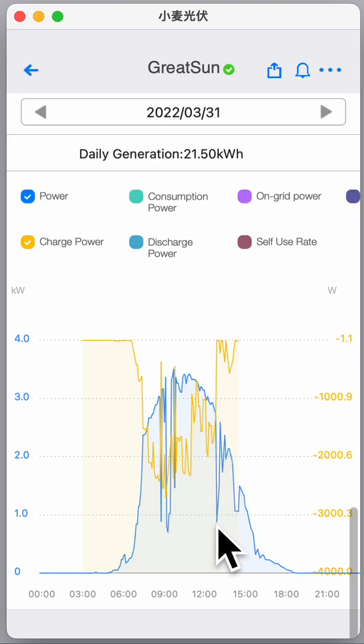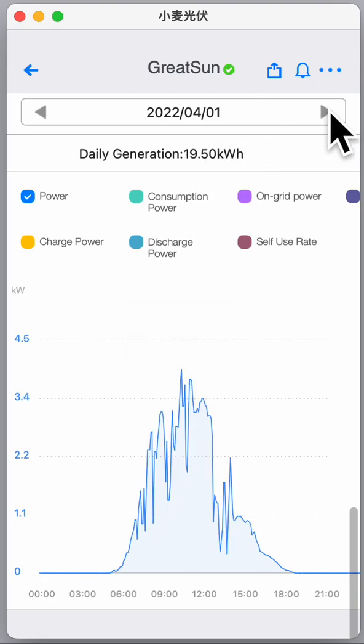When the production slowly goes down, or if the battery is so full that the inverter shuts down production, you don't get the battery charged. But as soon as we need more because the air cons kick in, it gets charged again. Going one day forward, you can see charging is stopped because the battery was already full, then it's charging with more than 3000 watts. The inverter limits at 80 amps and 50 volts, so my maximum charge is 4 kilowatts.